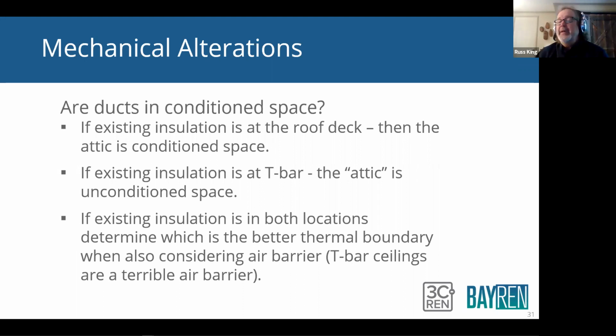If the existing insulation is in both locations, it's kind of a judgment call at that point, and you have to decide which is the better surface, which is the better thermal boundary. Is it the roof where the insulation is, or is it the T-bar ceiling? Usually it's going to be the roof, because T-bar ceilings actually make a terrible air barrier.